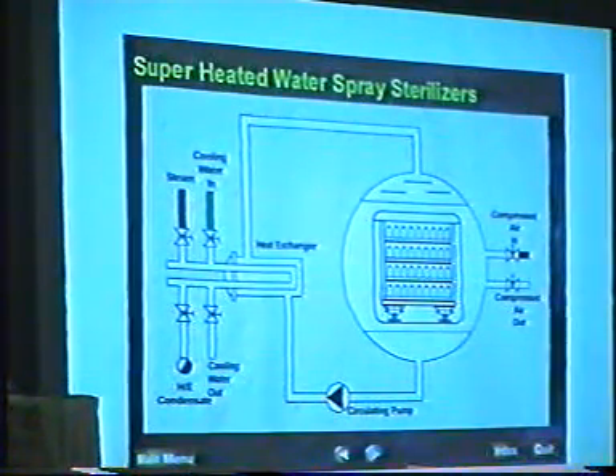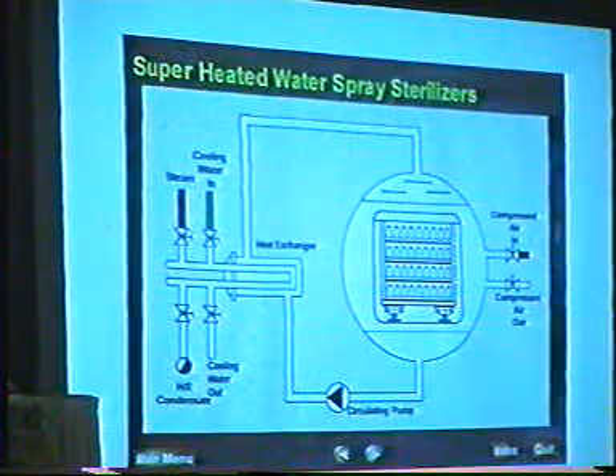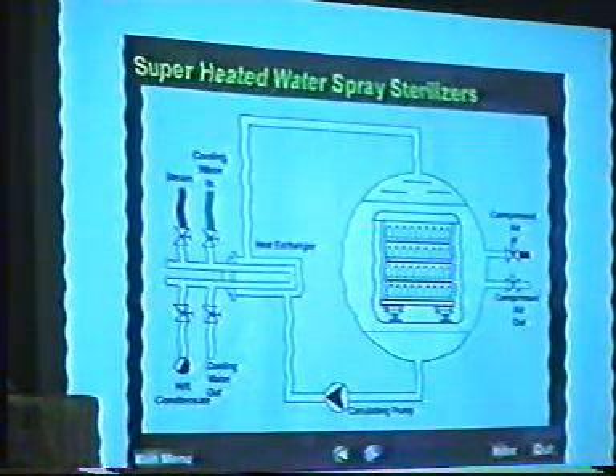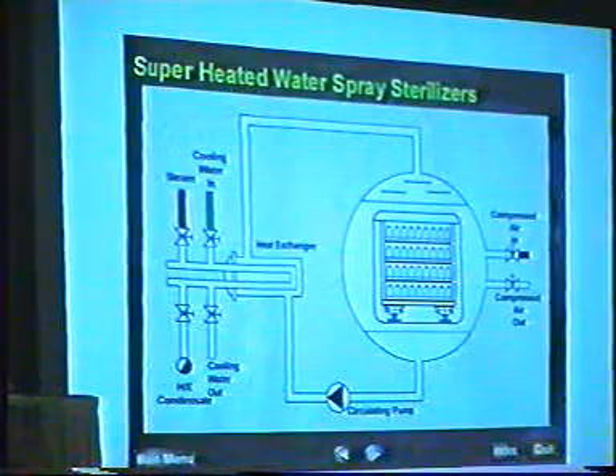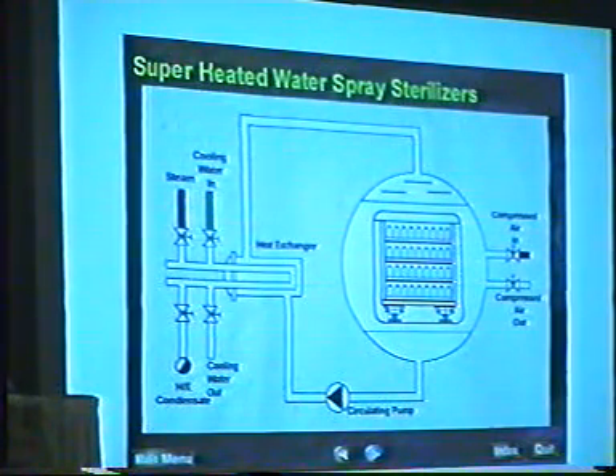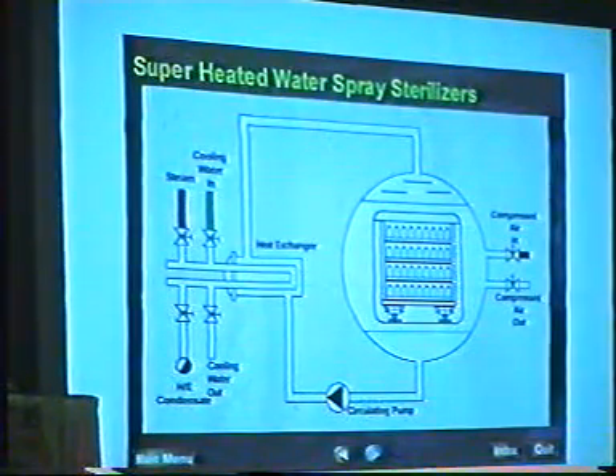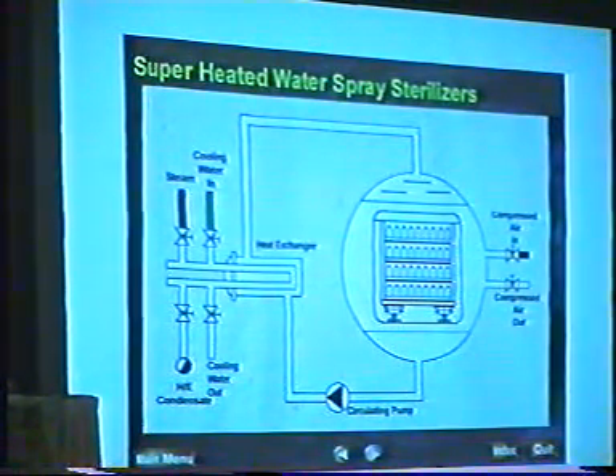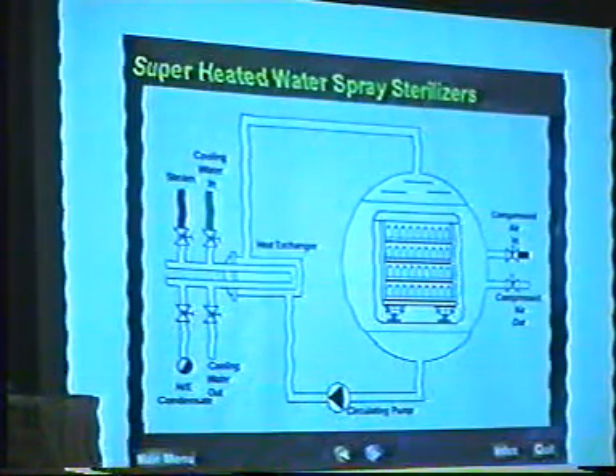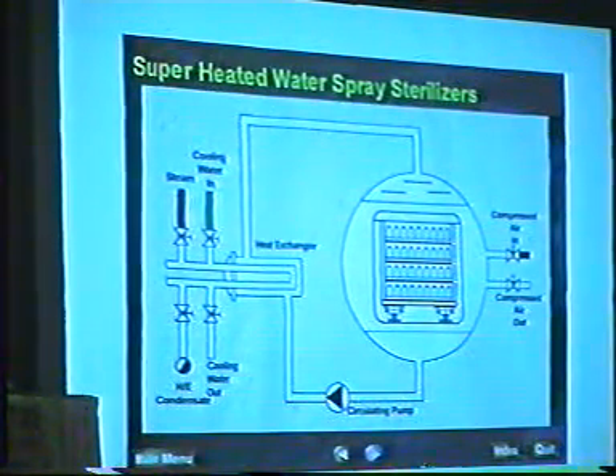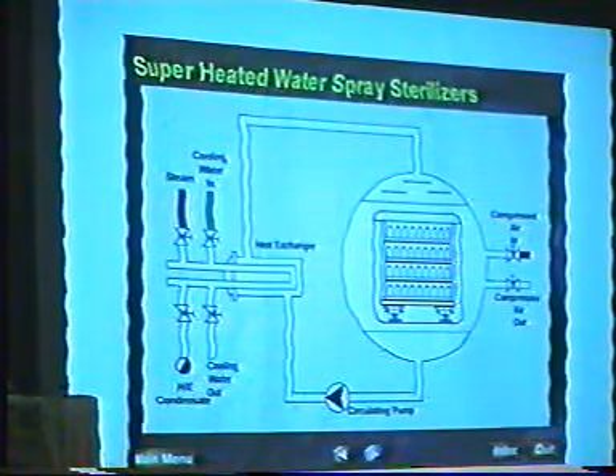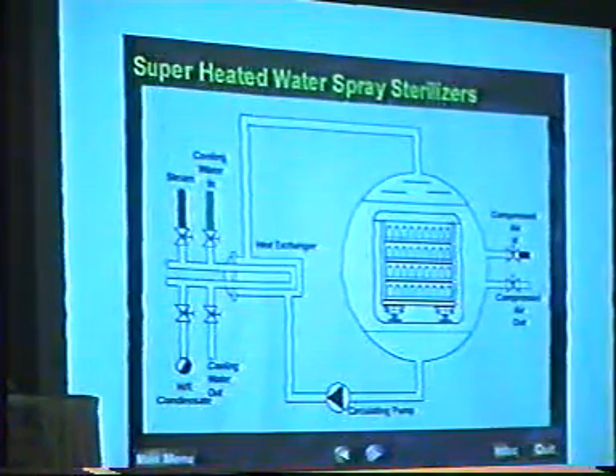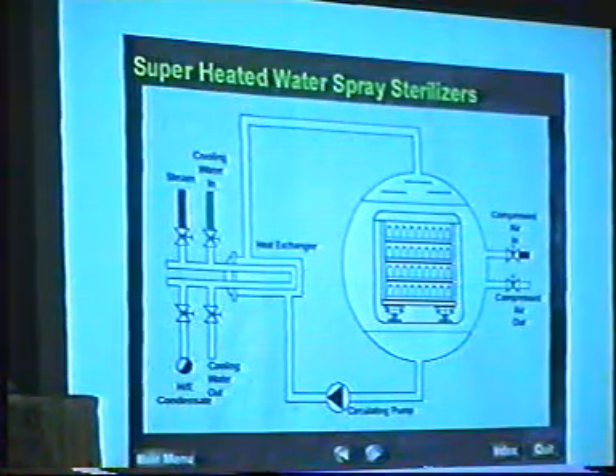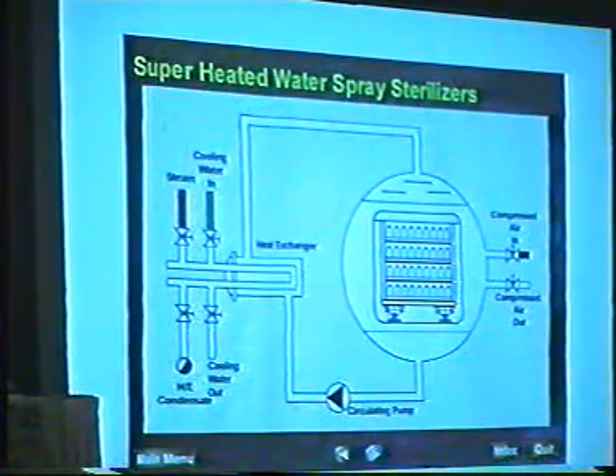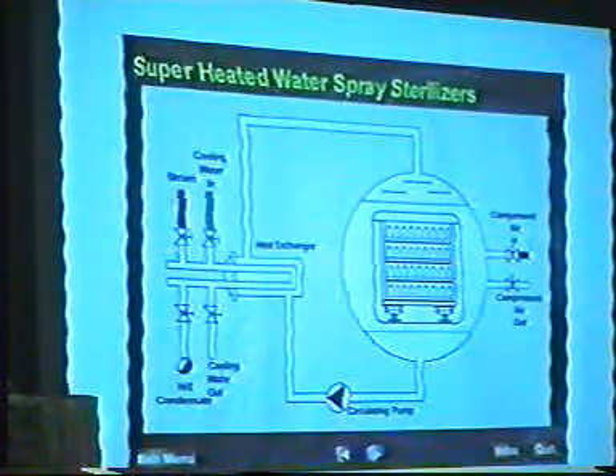However, the superheated water spray sterilizer takes care of these two vital issues very simply by heating the circulating water indirectly. So the main machine is equipped with a heat exchanger. There is a small quantity of water filled in the machine, which could be WFI, which could be filtered water, that is circulated at a very high velocity, and in the heat exchanger you give plant steam and heat this water. So plant steam does not come in contact with the load. Mind you, this circulating water, when it is undergoing the process, itself becomes sterile. So when you are cooling with the sterile medium, all the latest requirements as required by various authorities are met so far as superheated water spray sterilization.